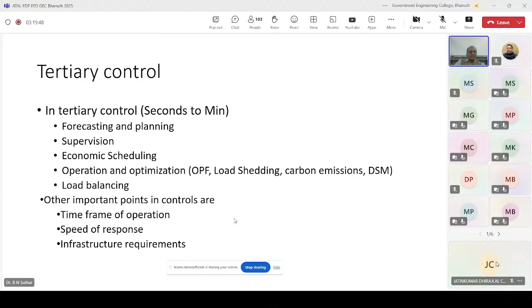Another important point is how fast the controller works and in what time frame. If an operation needs to happen in milliseconds but instead takes seconds or tens of seconds, it creates stability problems in the system. So the time frame of operation, speed of response, time constants of these controllers or devices, and the infrastructure requirements all matter. The infrastructure requirements mainly involve communication links, data transmission, data collection, and power electronics devices.